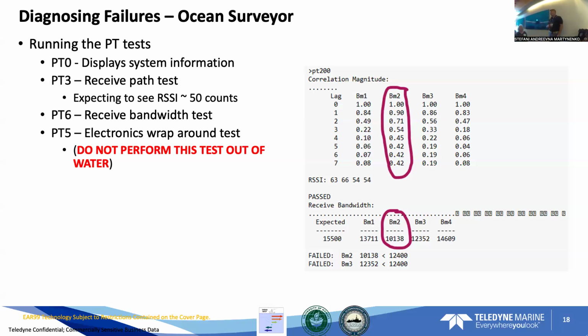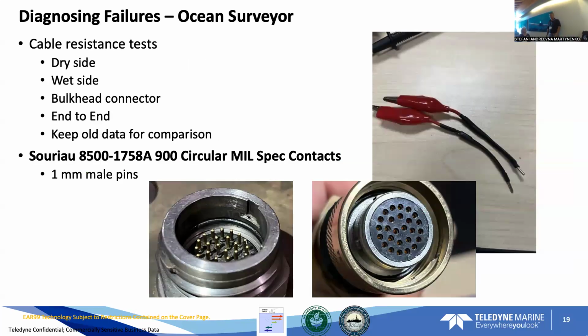So if we run the PT200 test and we see the noise, then we know something's gone wrong. Then the PT5 test is a transmit test, and if you're not in water, don't ever run that. And so when you type PT5, it asks you, is this in water? Okay, well, say yes. This comes to our biggest point, the cable resistance check, so we can tell what crystal is bad.